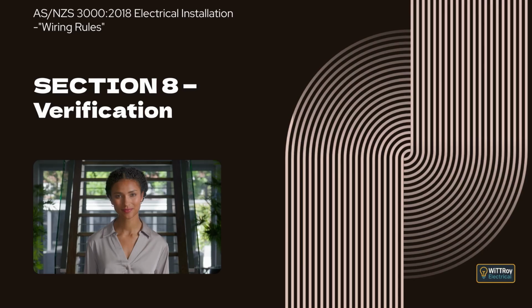They also explain that EFLI testing is not required for RCD-protected socket outlets because the operating time of the RCD provides additional protection. The notes further explain that EFLI testing is generally not required for circuits supplying equipment other than socket outlets, and that for other circuits the maximum trip time requirement must still be met, even if EFLI testing itself is not required.